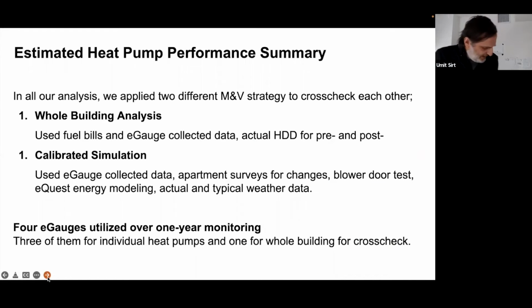For our measurement and verification, we applied two different approaches to cross-check with each other. One was whole building analysis, using utility bills and collected data via e-gauge, along with actual heating degree days for the pre- and post-install periods. The other was calibrated simulation, using the collected e-gauge data, apartment surveys, and a blower door test to build an eQuest energy model mimicking the building pre-retrofit, then applying the changes made and running both actual and typical weather data.